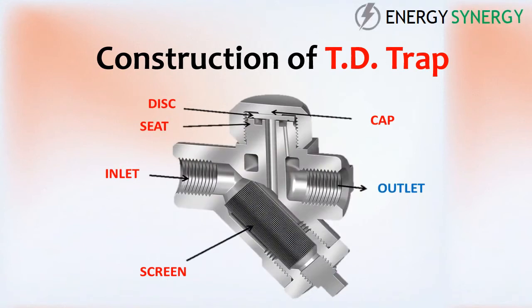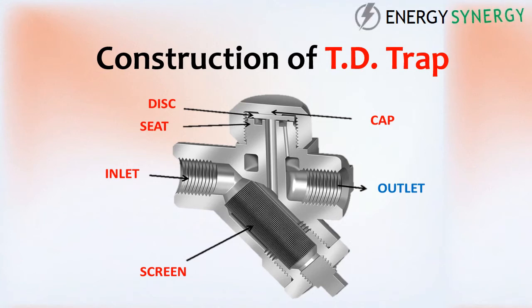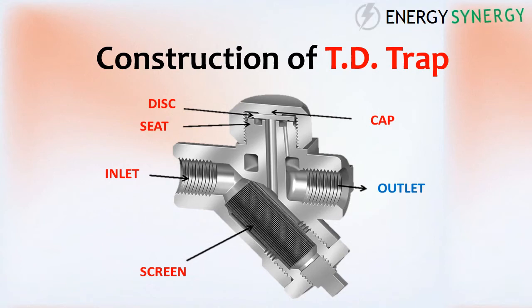Let's see the construction of a TD trap. This is the inner image of the thermodynamic steam trap. Inside there is space for condensed steam, a steam inlet, and an outlet. There is a screen between and below the inlet and outlet which catches contaminants present in the condensate.